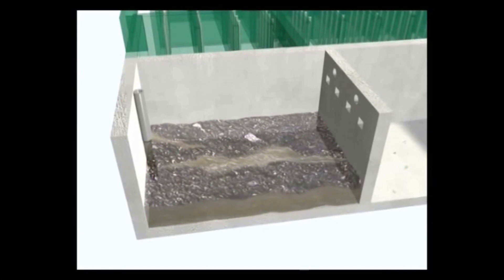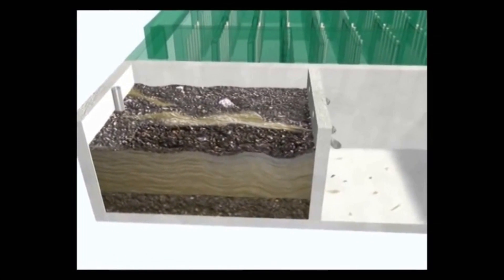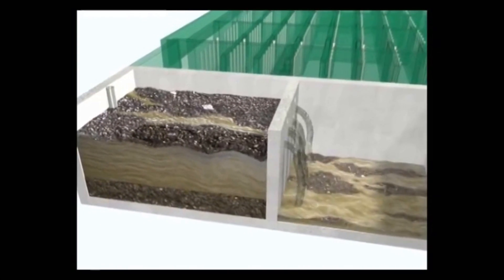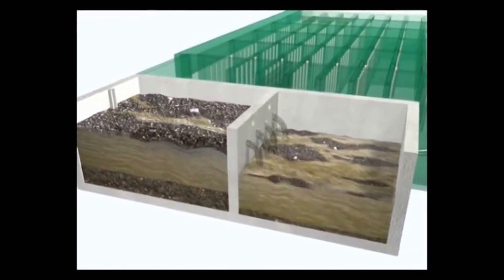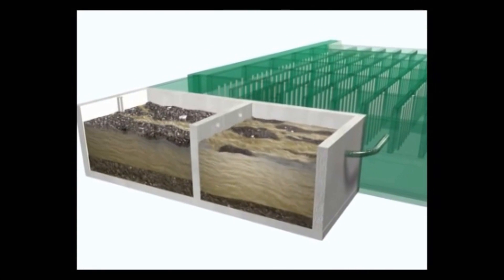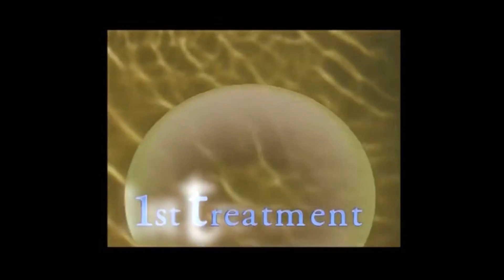The first stage is the settling tank. Here, contaminants are retained by flotation and sedimentation, which happens through natural separation of heavy particles. The heavy particles sink down and lighter particles are retained by flotation.